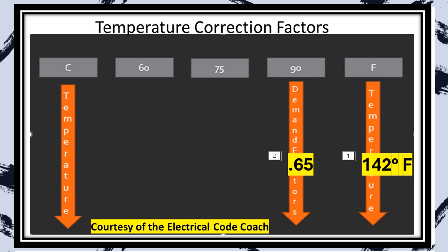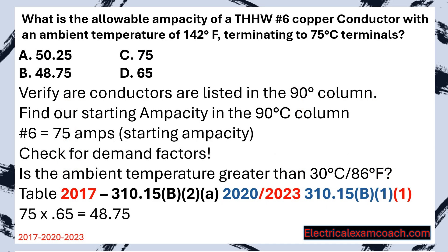We head to our respective temperature corrections table depending on our code cycle and find our correction factor. Start on the right-hand side because the question states Fahrenheit, go down to find the range for 142 degrees, slide over to the 90 degrees C column, and find the correction factor. We take our starting ampacity of 75 and multiply it by the correction factor, giving us a new allowable ampacity of 48.75 amps. Select B.